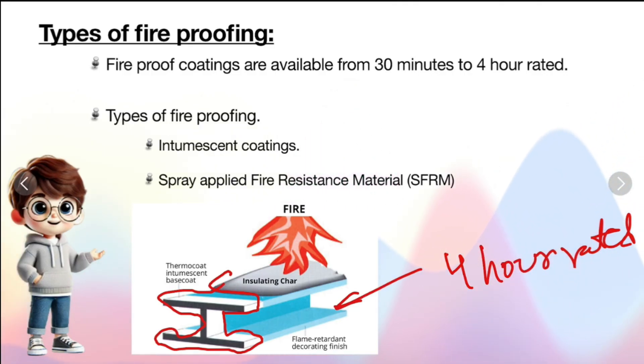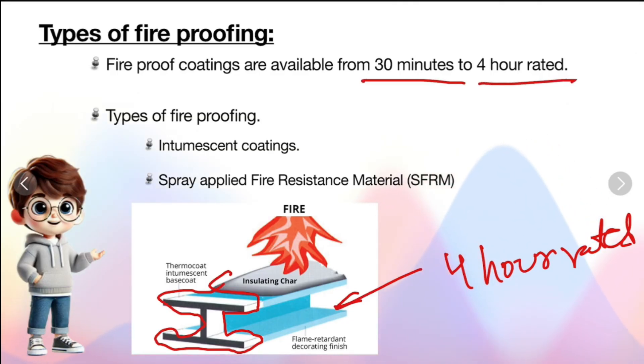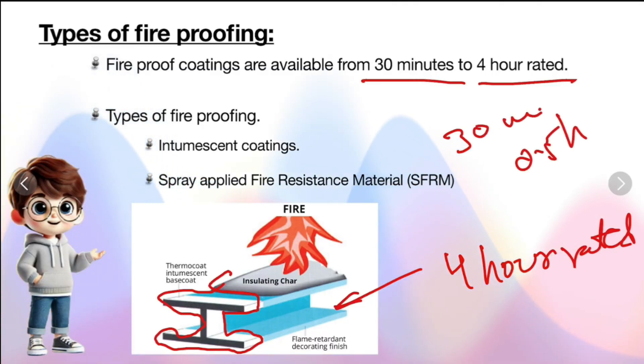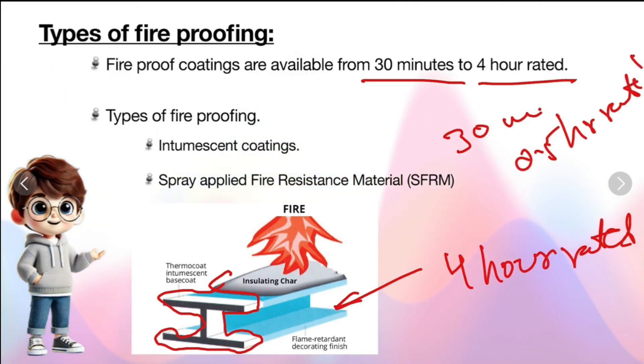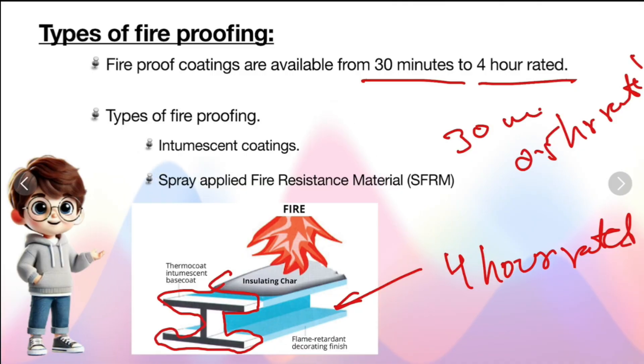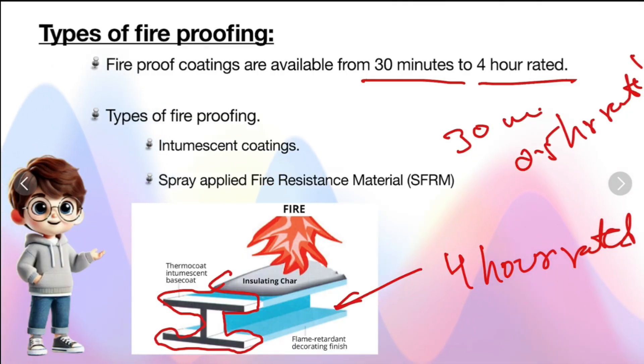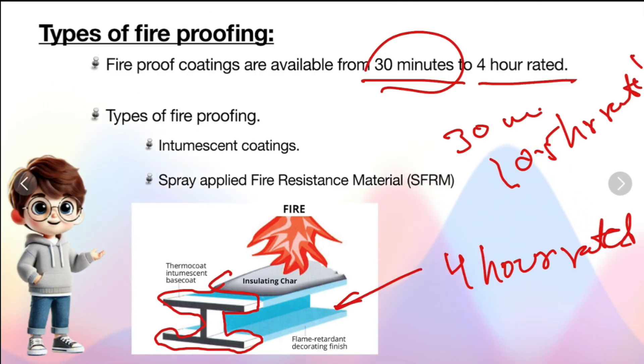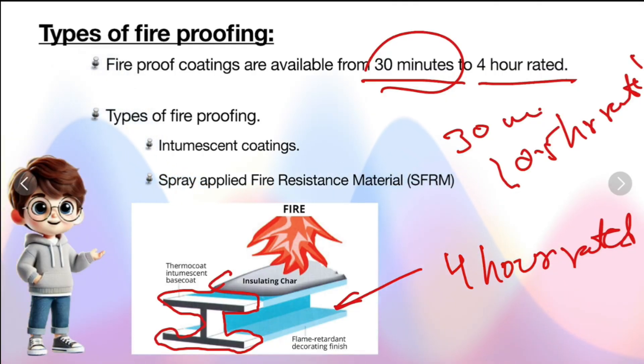Let's see what 30 minutes and 4-hour rated means. For example, if it indicates 30 minutes or 0.5-hour rated, it means that when this 0.5-hour rated coating is applied on the steel and that steel is subjected to fire attack, up to half an hour that steel will not lose its strength properties. That is the meaning of 30-minute rated or 0.5-hour rated. In the same way, 1-hour, 2-hour, 3-hour, and 4-hour rated coatings also exist — intumescent coating will be up to 4-hour rated, but it is a costly process.